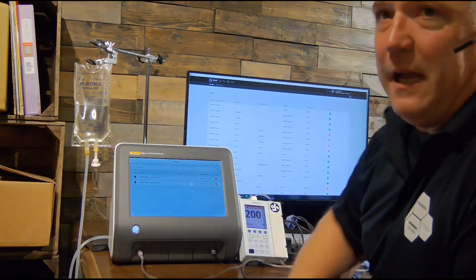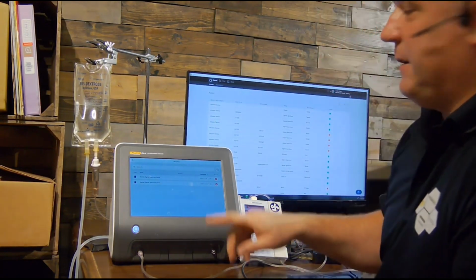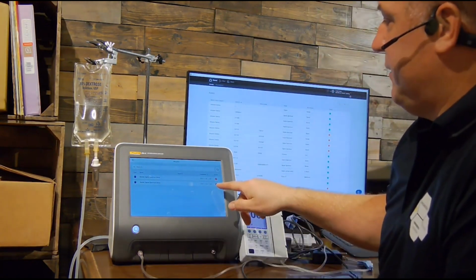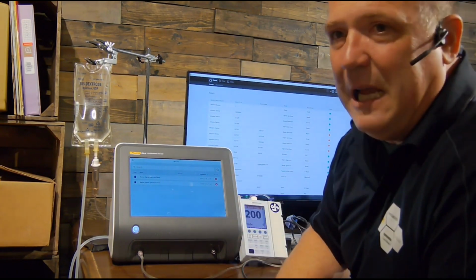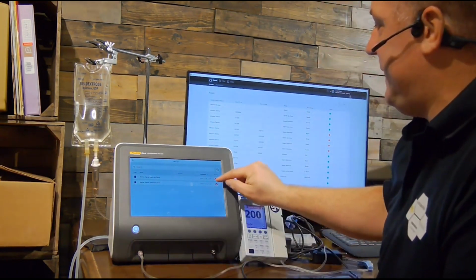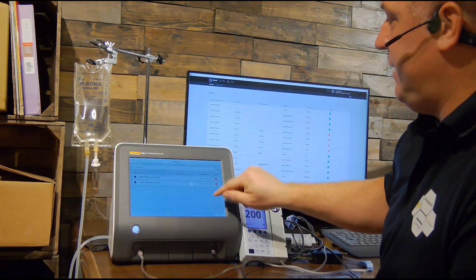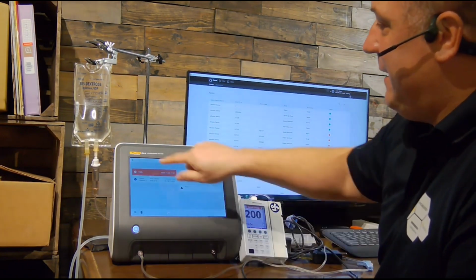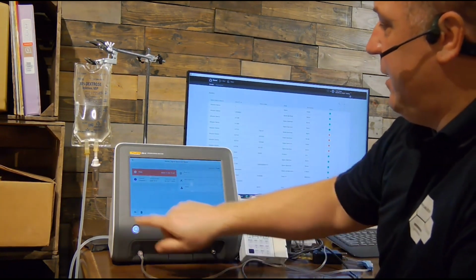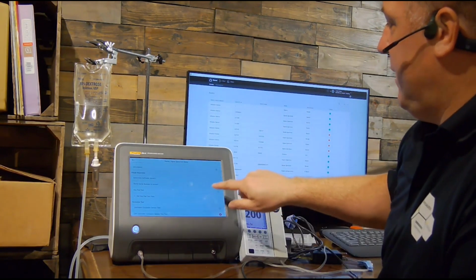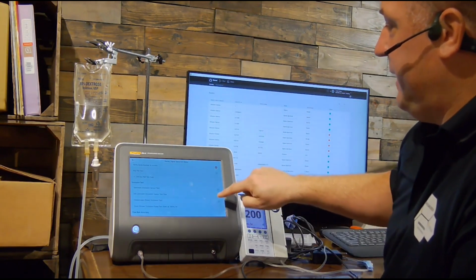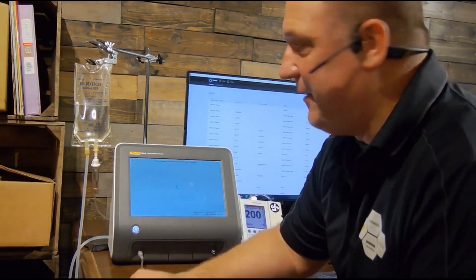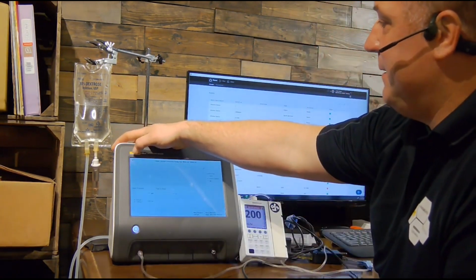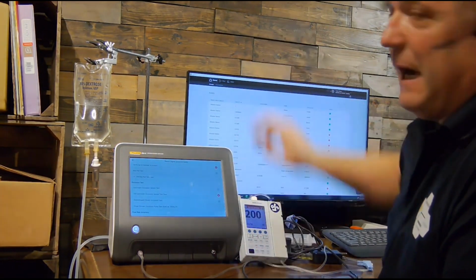So here's every test I've run with the IDA-6. You can see I've been doing demos and I've failed the procedures, so I have red X's. If I passed it, I'd have a green light here, and I could go into these, and I can see what happened. I can go down here to my notes, and I can see, oh, it failed right here, and it failed here. I can't change anything on these screens now because I already finalized it, but I can see what happened without going back to my PC.